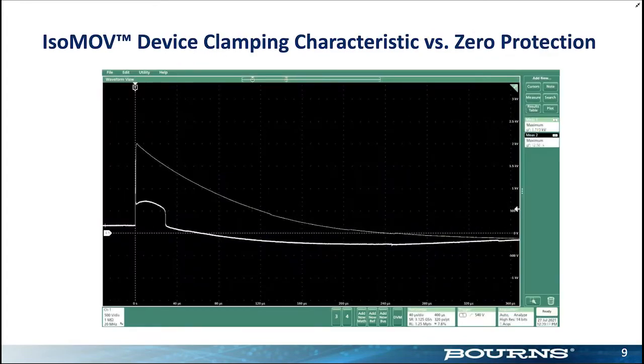So if I blow up that waveform and I zoom in on that clamping voltage, you'll see the surge in yellow. That's a 2 kV surge. And the white is the IsoMOV clamping voltage. You can see that broad area is around 700 volts. That's the MOV clamping. And that front end, that spike goes up to about 1.5 kV. That's how much voltage it takes to spark that GDT. And you're looking at that, and you're saying, oh my gosh, that's not much different than the 2 kV voltage that my surge is. My circuit is going to see that white voltage. I'm still going to see 1.5 kV. Gosh, that doesn't sound very good to me at all.